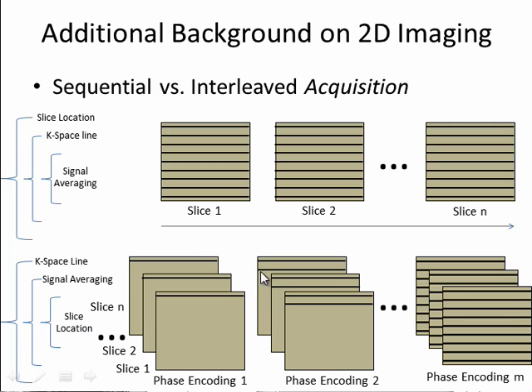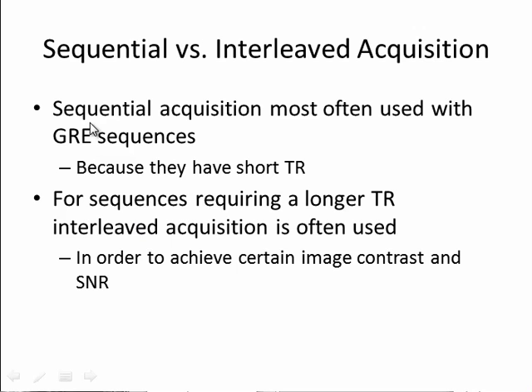Then we go to the next slice, do any averaging on that line. Then the outer loop — we move to the next phase encoding line, which would be the third line, and so on until we acquire all of our lines. You can see that the acquisition order is quite different between these two methods. Certain pulse sequences are more suited for sequential, and certain sequences are more suited for the interleaved type. Gradient echo sequences are good candidates for sequential acquisition because they have a short TR, while sequences that need a longer TR are good candidates for interleaved acquisition so that you can achieve a certain image contrast and signal-to-noise ratio.